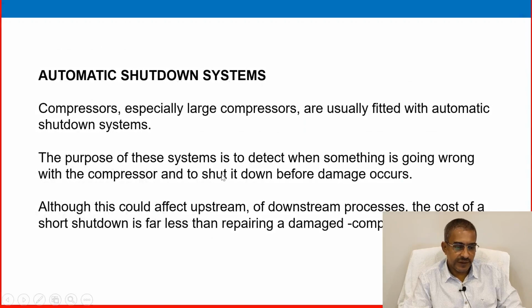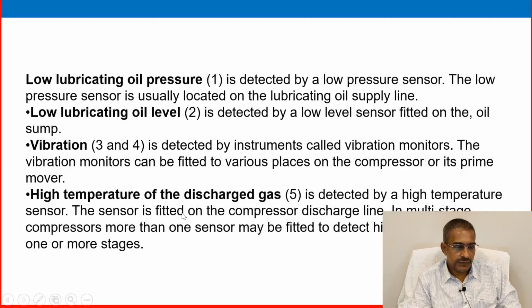Automatic shutdown system. Compressors, especially large compressors, are usually fitted with automatic shutdown. The purpose of this system is to detect when something is going wrong with the compressor and to shut down before the damage occurs. Although this could affect upstream and downstream processes, the cost of a short shutdown is far less than repairing a damaged compressor. So generally, what are the shutdown conditions we can provide in a centrifugal compressor?